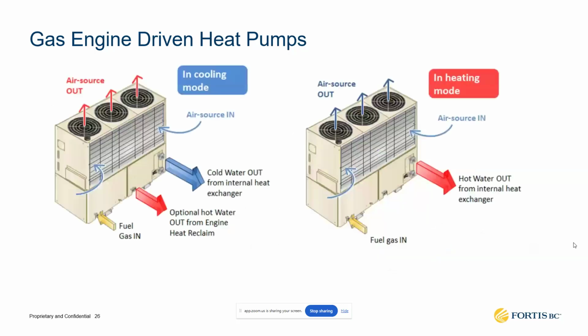And another advantage, and this is a product from Yanmar that I'm showing here on these graphics, is that in cooling mode, the unit has an option to provide hot water from the exhaust gas heat that is being recovered into producing hot water for the building. Although this function is not available in heating mode.